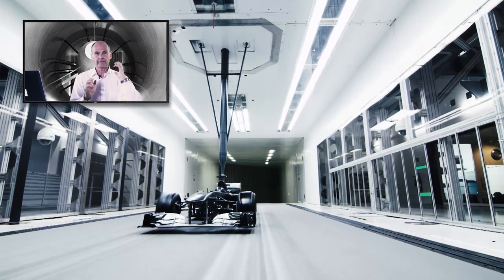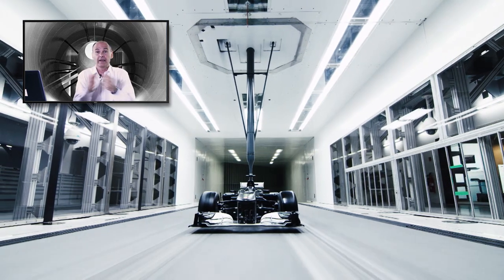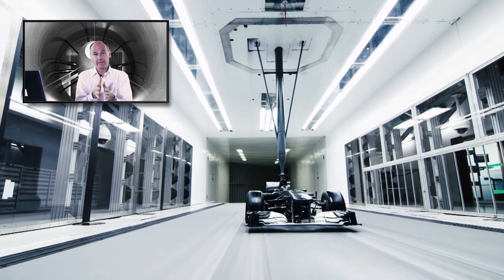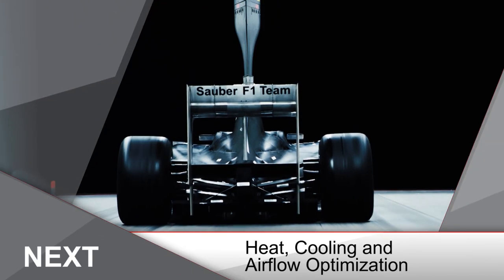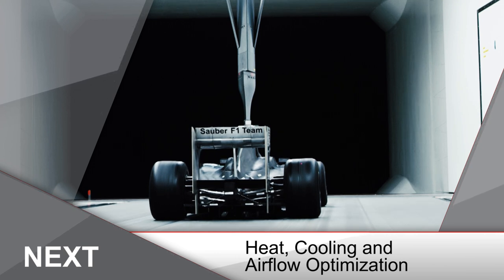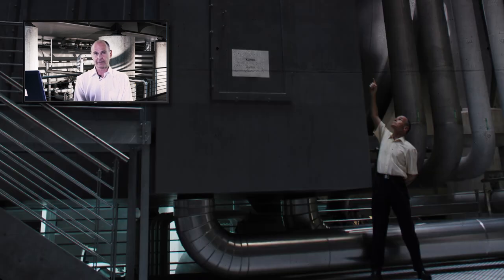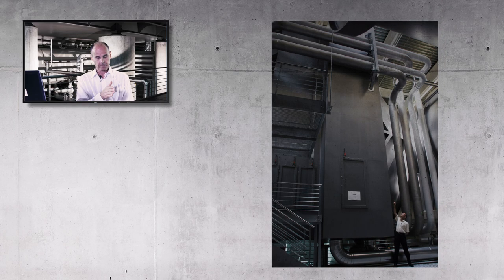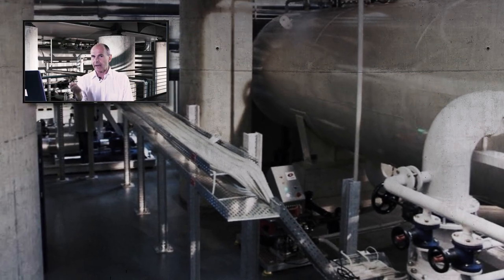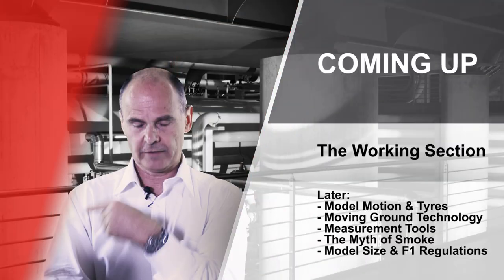We also have to manage the heat we put into the air. We have a 3 megawatt fan — those three megawatts effectively generate motion and heat, warming the air up as we drive it forward. We have to take that heat out of our airline. In one of our legs, we have a huge radiator — about nine metres by nine metres in size. We pump cool water through that radiator as fast as we can, regulating the temperature of the water.